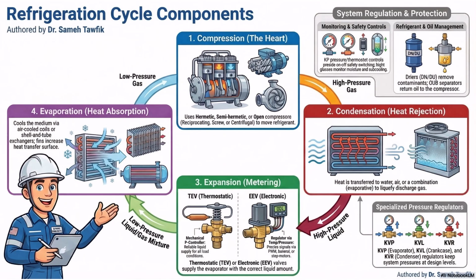How does it sense it? It uses a small, sealed, temperature-sensing bulb clamped to the exit pipe of the evaporator. Oh. Inside that bulb is a tiny charge of its own refrigerant. As the exit pipe gets warmer, meaning the evaporator is starving and the superheat is too high, the fluid inside that little bulb boils. Oh, wow. Yeah, it expands, travels down a capillary tube, and physically pushes down on a diaphragm. And that diaphragm opens the valve. Exactly. That diaphragm pushes against a spring, forcing the valve open to let more liquid in. That is brilliant. The heat itself provides the physical mechanical force to push the door open. Yeah. And then as it cools down, the pressure in the bulb drops, the spring pushes back, and the door closes. It's a self-regulating physical loop. Exactly. It acts as a proportional controller.